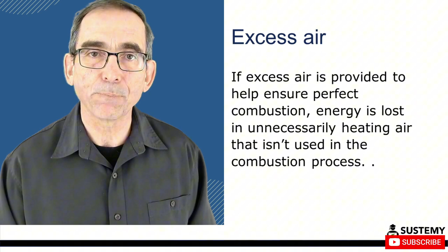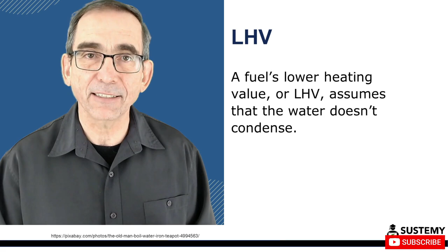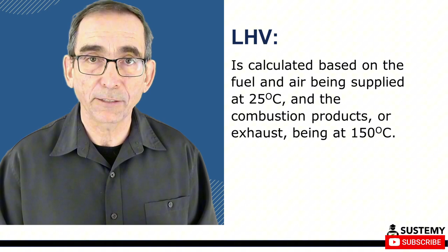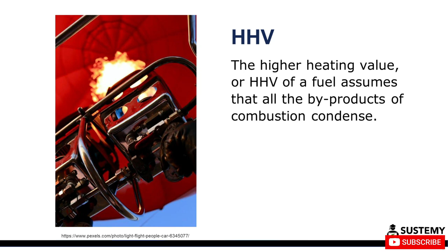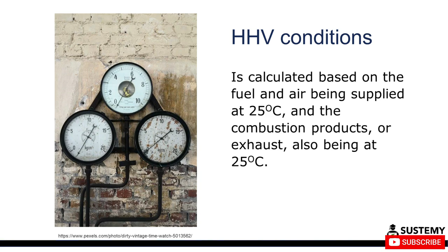As a byproduct of combustion is always water, the amount of heat delivered depends on whether that water is fully or partially condensed or not condensed at all. If it's fully or partially condensed, that will increase the amount of heat that is provided, as is the case in a condensing flue hot water boiler. A fuel's lower heating value, or LHV, assumes that the water doesn't condense. It's calculated based on the fuel and air being supplied at 25 degrees Celsius and the combustion products or exhaust being at 150 degrees Celsius. The higher heating value, or HHV, of a fuel assumes that all the byproducts of combustion, particularly water, condense and that the final temperature is also 25 degrees Celsius.